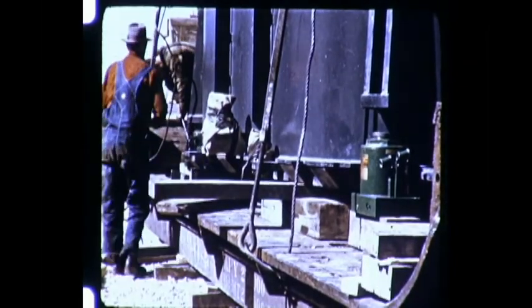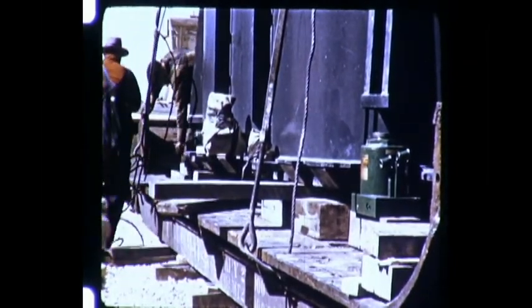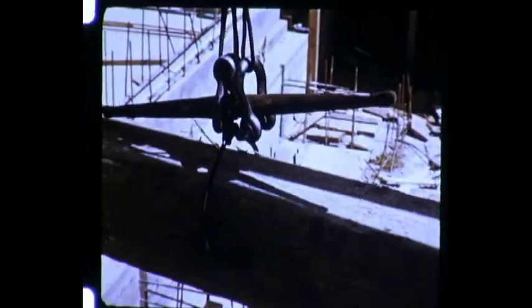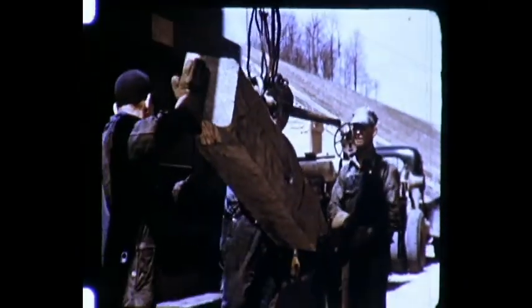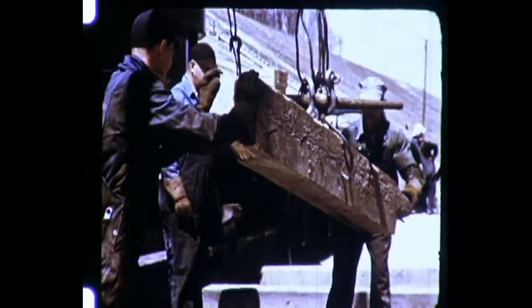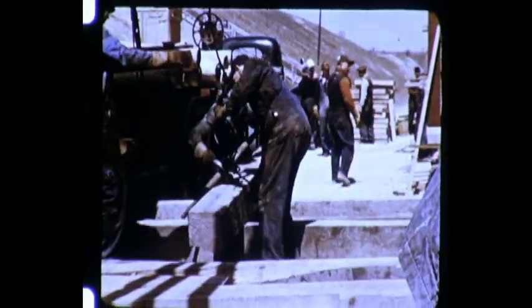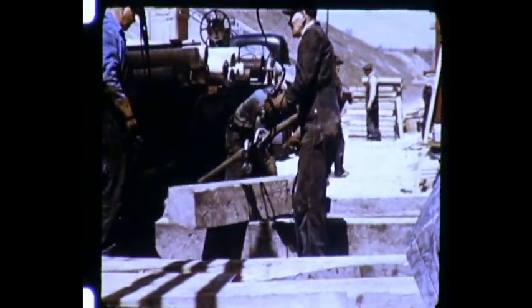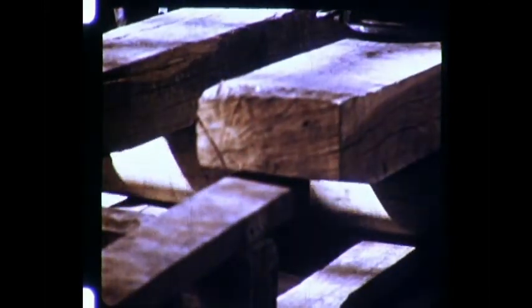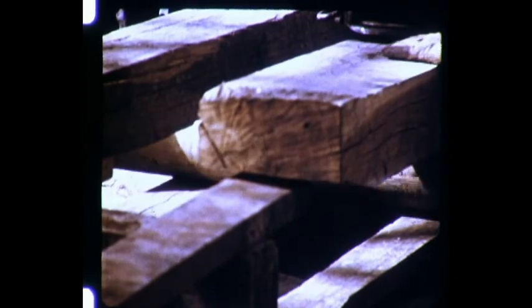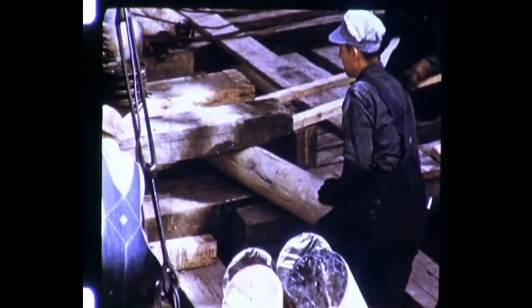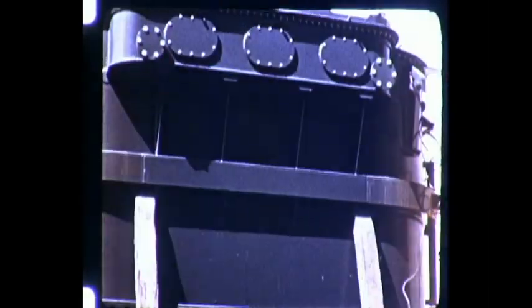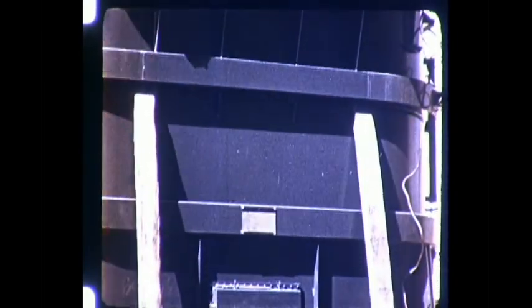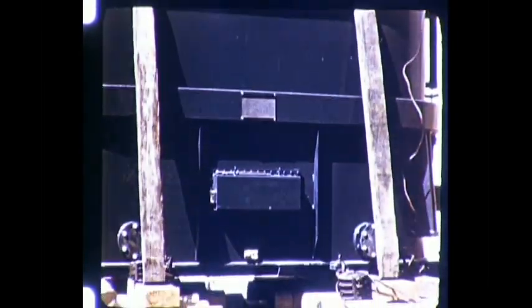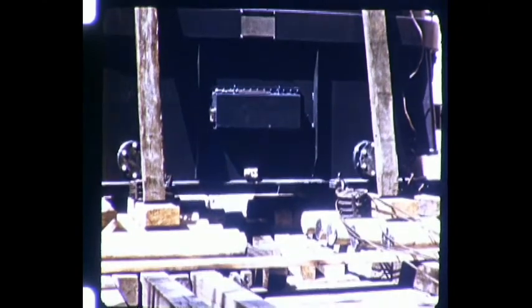While the unit is being raised to a height slightly above that of the concrete pad, large timbers are brought in to form the cribbing over which the transformer will move. And again, a carefully laid out crisscross pattern of supports is used. At Oak Creek, however, large wooden rollers rather than steel skid beams are used to move the transformer to the pad. The angle bracing between the transformer and the wood beam runners is added to provide additional support during the move across the cribbing.